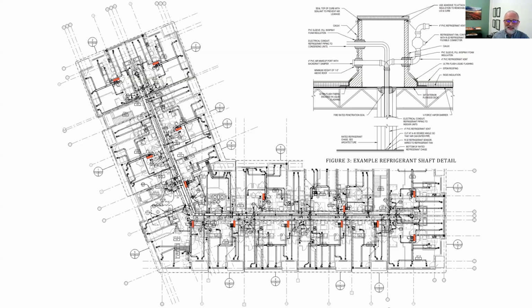So it's easy to see that these shafts are going to be costly and will represent new challenges for passive house buildings to meet air sealing requirements. There's also kind of a constructability issue associated with these shafts, and that is that because of the class of refrigerant, the refrigerant piping has to be inspected. So the shafts have to be built on 3 sides and the refrigerant piping installed and then inspected, and then the shaft gets closed up. So it's kind of a hassle.